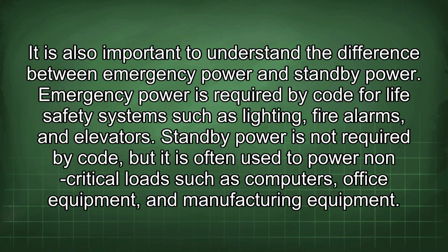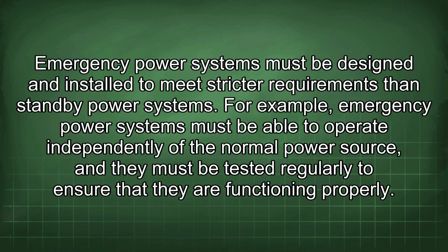It is also important to understand the difference between emergency power and standby power. Emergency power is required by code for life safety systems such as lighting, fire alarms, and elevators. Standby power is not required by code, but it is often used to power non-critical loads such as computers, office equipment, and manufacturing equipment. Emergency power systems must be designed and installed to meet stricter requirements than standby power systems. For example, emergency power systems must be able to operate independently of the normal power source, and they must be tested regularly to ensure that they are functioning properly.